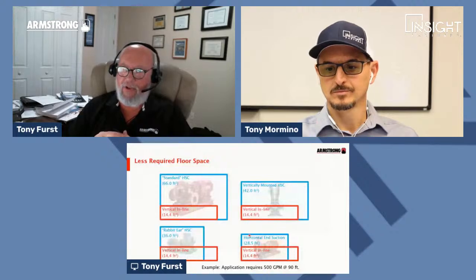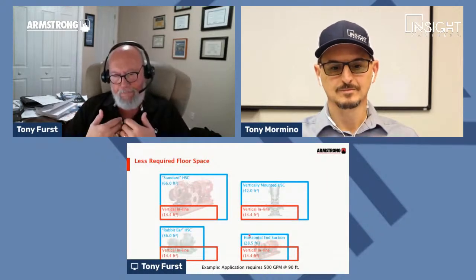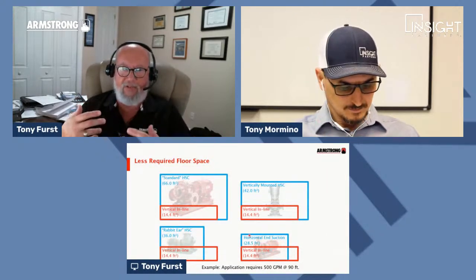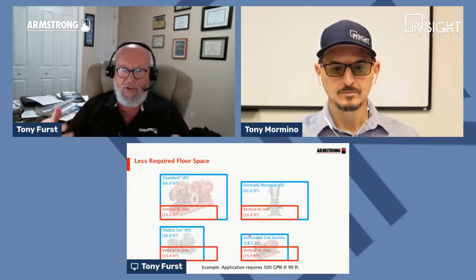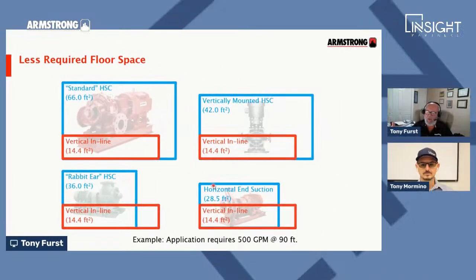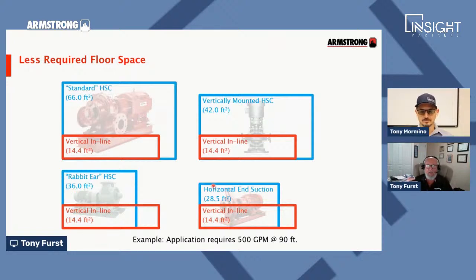So the next thing is we talk about floor space, and end suction pumps take a lot of floor space. So if I look at a pump, 500 GPM, 90 foot head, not a huge pump, but not a small pump. And if I size a typical horizontal split case for those conditions, that pump takes about 66 square foot of floor space. And that includes the pump and the housekeeping and the inertia base and all that stuff that goes underneath of it. If I look at a vertical mounted HSC, which is basically the same as a horizontal split case pump, but it's just standing on its end, it's 42 square feet.